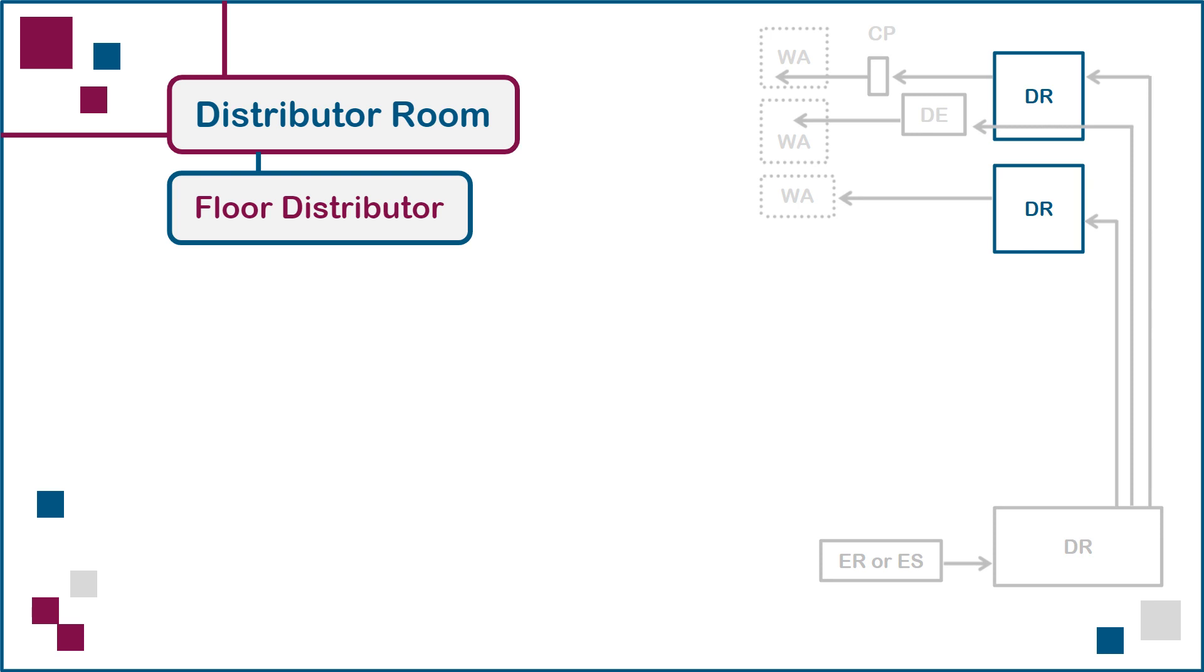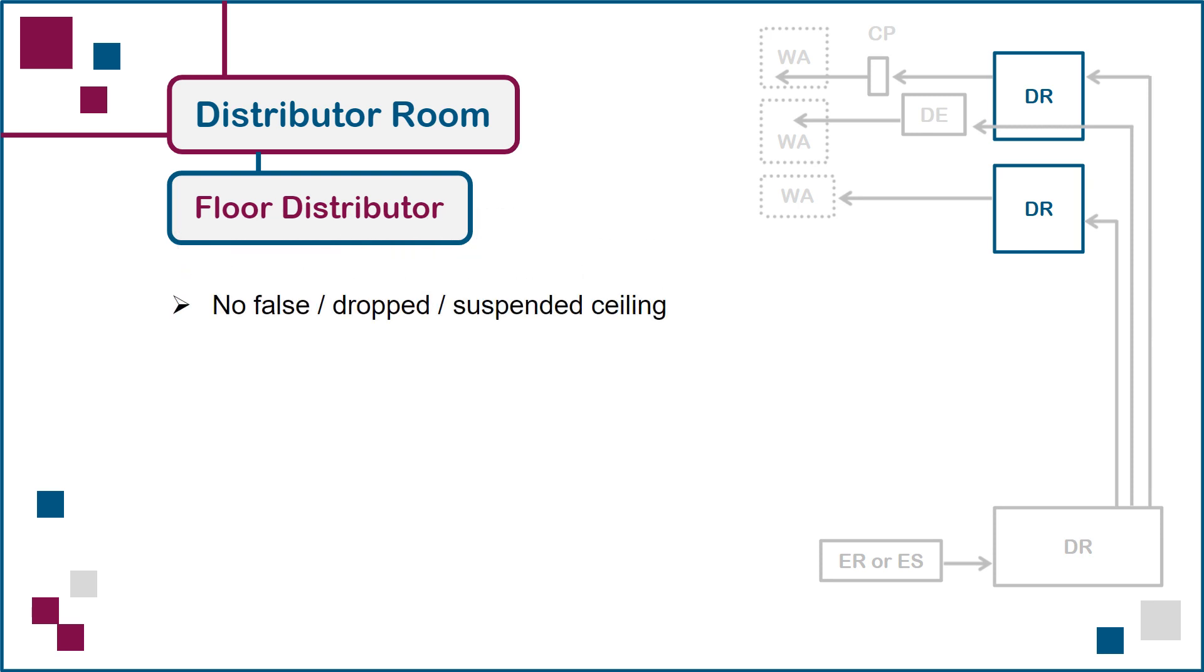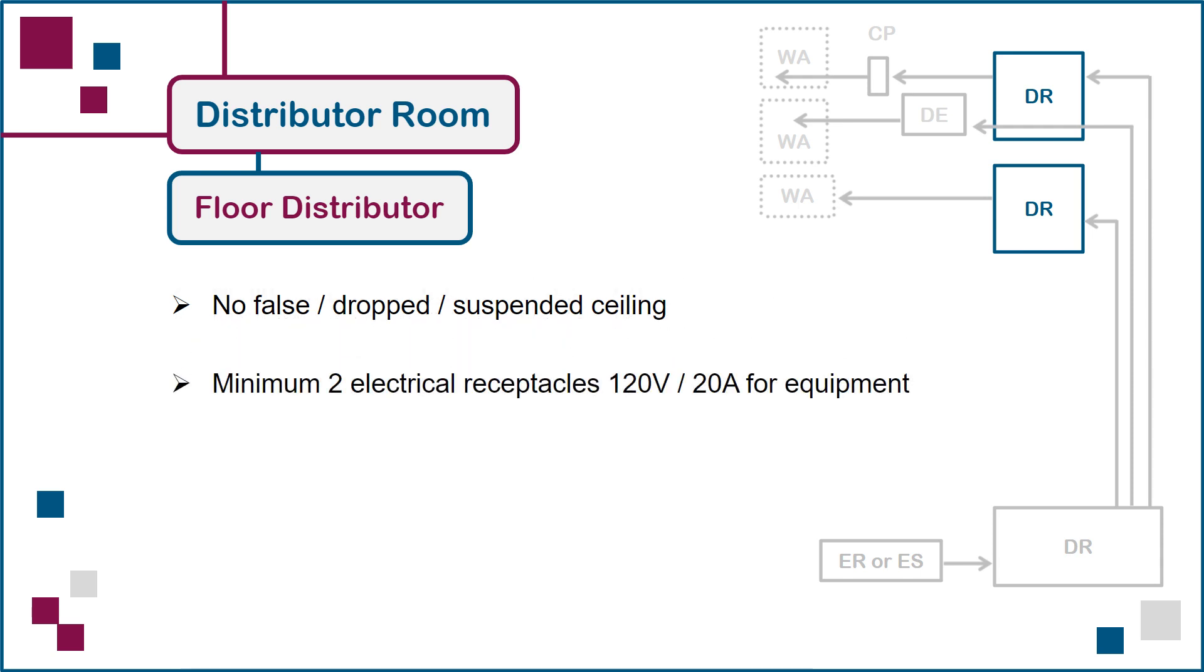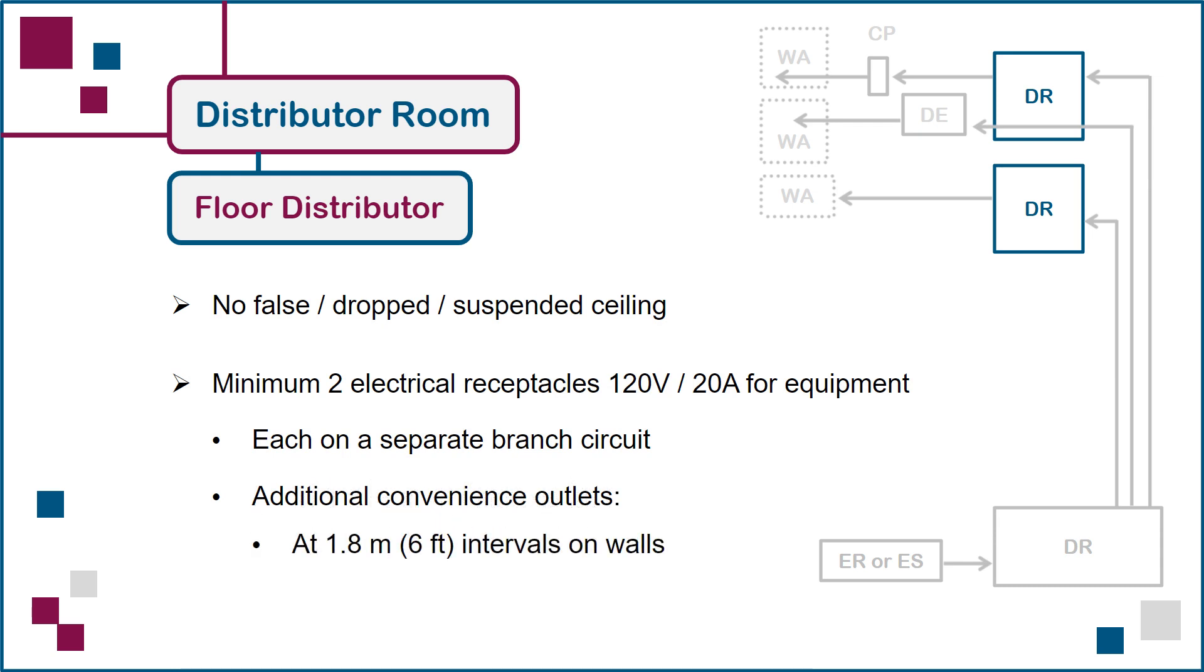Unlike the office spaces in a commercial building, the ceilings in distributor rooms should be easily accessible, not covered for aesthetic purposes with additions like ceiling tiles. Unobstructed ceiling access in all distributor rooms facilitates future cable management, such as the addition of equipment outlets or the upgrade of cabling links. And here are some TIA guidelines intended to provide additional flexibility in the room to plug-in devices, both permanently, such as new network equipment, and temporarily, such as battery chargers for tools or test instruments brought in by technicians.